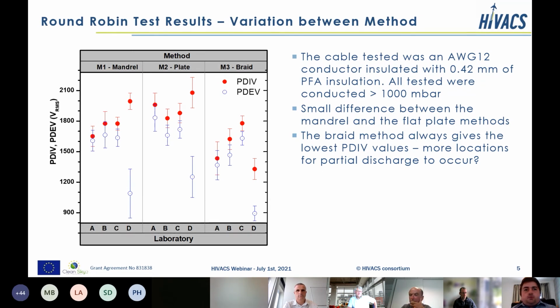And what we see is for the mandrel method, we get around 1650 to 2000 volts RMS for the PDIV. For the plate, it's a little higher, around 1800 to 2100 volts RMS. The most notable difference is that the braid method gives considerably lower PDIV results than the other two methods. The PDEV results follow the same trend as the PDIV results.